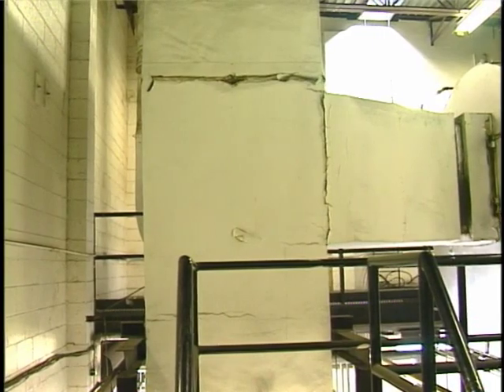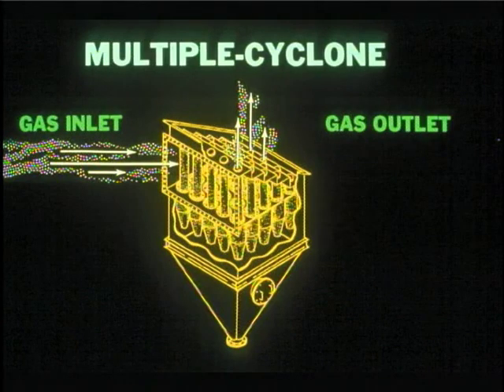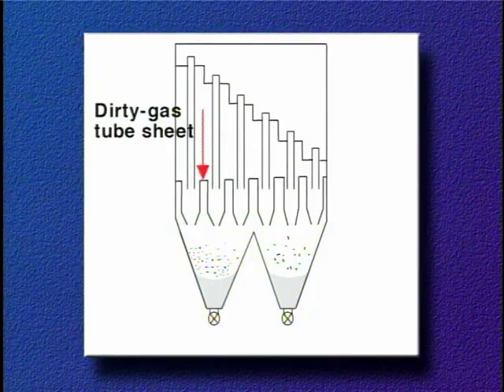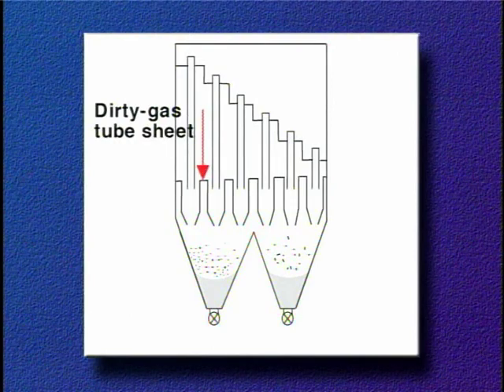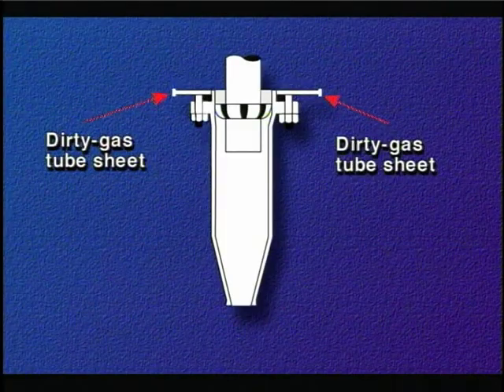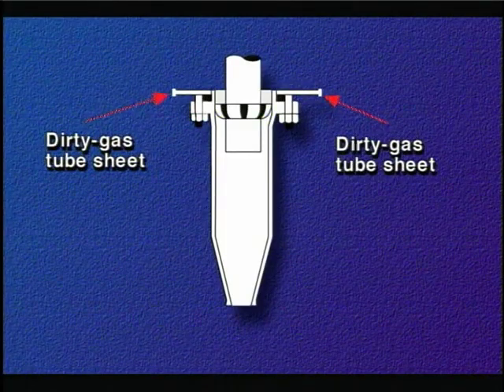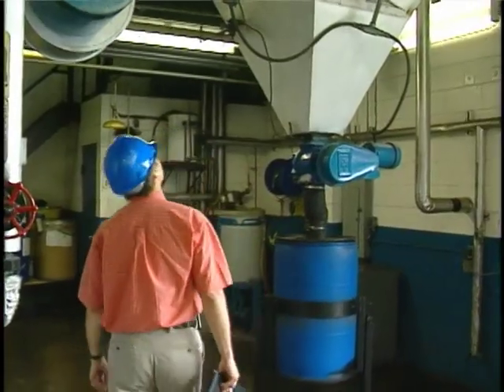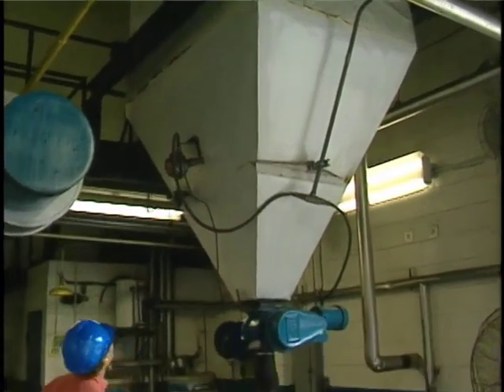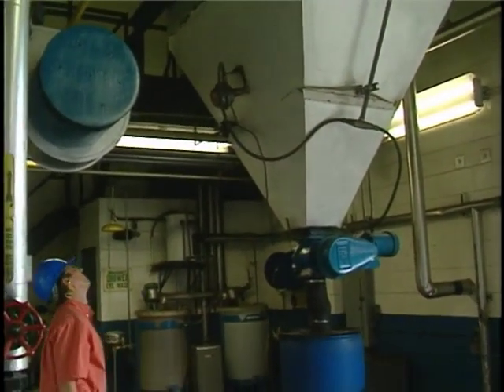Multi-cyclone collectors are divided into three areas by metal plates referred to as tube sheets. The dirty gas stream enters the collector between these two tube sheets. The lower, or dirty gas tube sheet, separates the inlet gas stream from the lower casing and hopper area of the collector. The cyclones are mounted in holes in this tube sheet and extend into the lower casing. Particles exiting the individual cyclones are collected in a common hopper section below the lower casing before being removed for disposal.